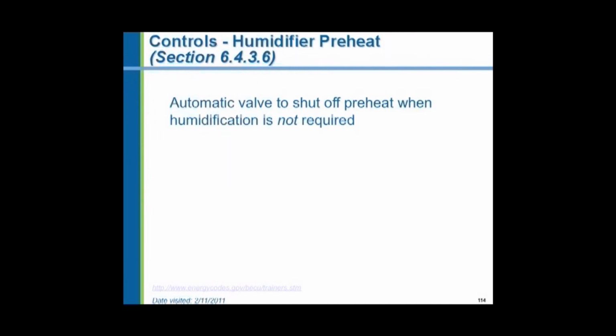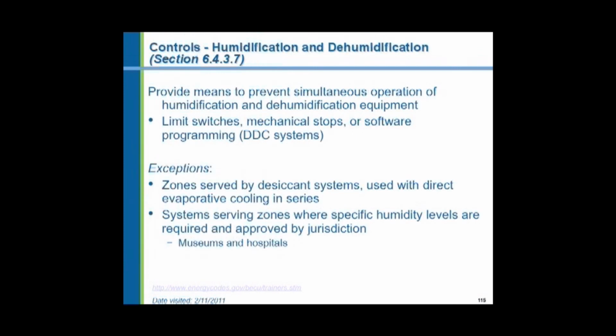Automatic valves are required for humidifiers. If the humidifier has a preheat system, or if it boils, if it has a boiling chamber full of hot water and it evaporates and makes steam, when the system is not required, they don't want the boiling chamber hot. They don't want it to stay hot all the time if humidification is not required. You have to prevent the simultaneous operation of humidifiers and dehumidifiers, just like we did with heating and cooling. Make sure they don't operate at the same time. There are some exceptions.